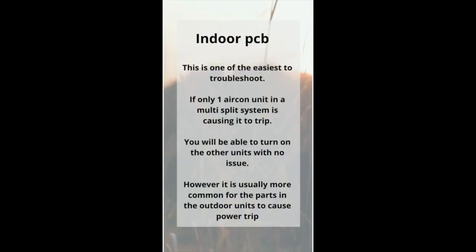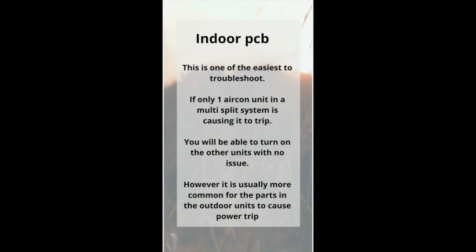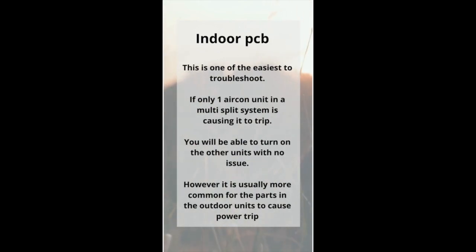If it is the indoor PCB, it is one of the easiest to troubleshoot. If only one aircon unit in a multi-split system is causing it to trip, you will be able to turn on the other units with no issue. However, it is usually more common for the parts in outdoor units to cause power trip.